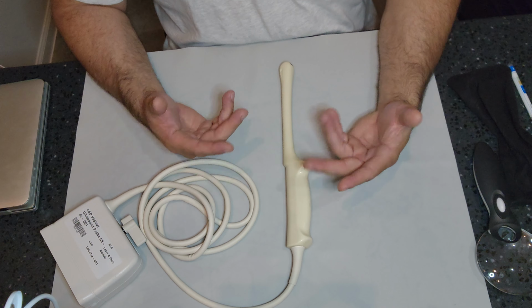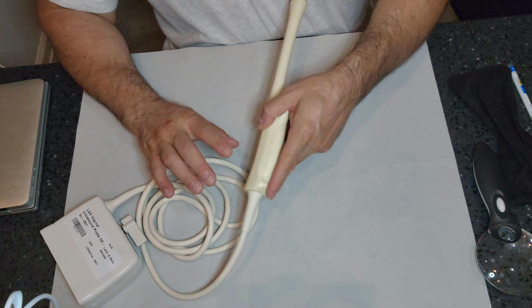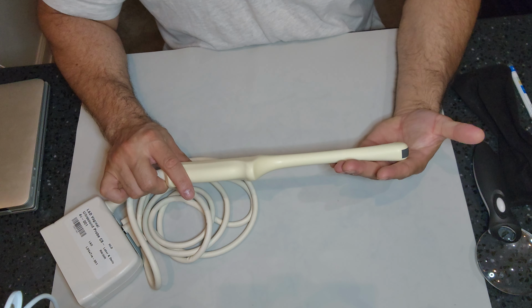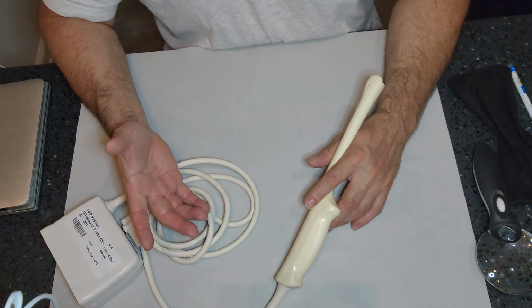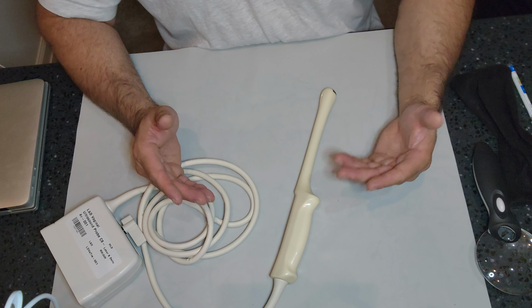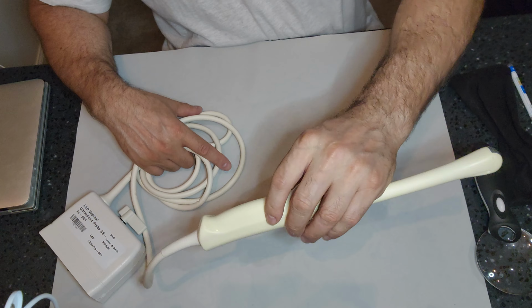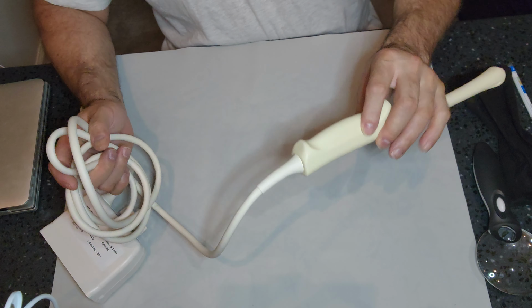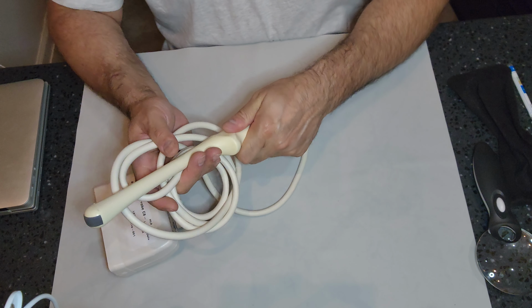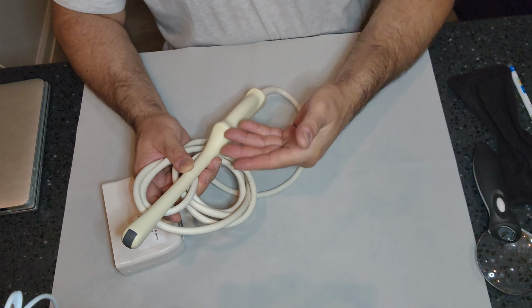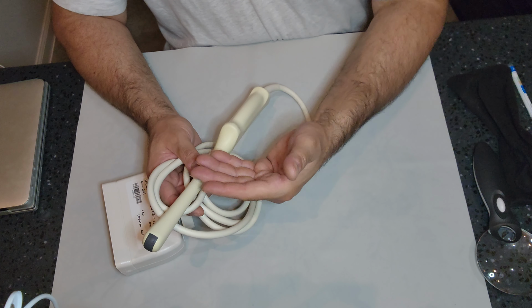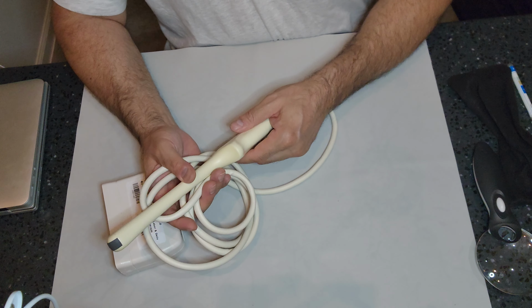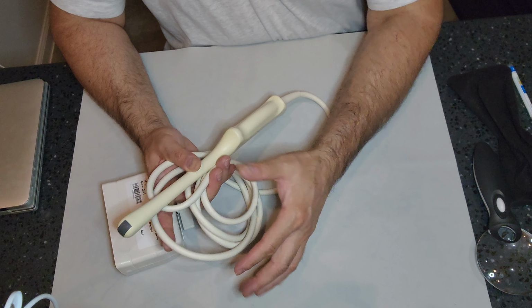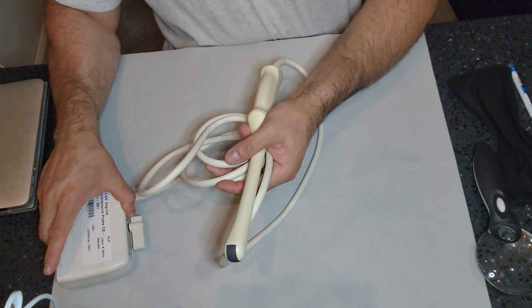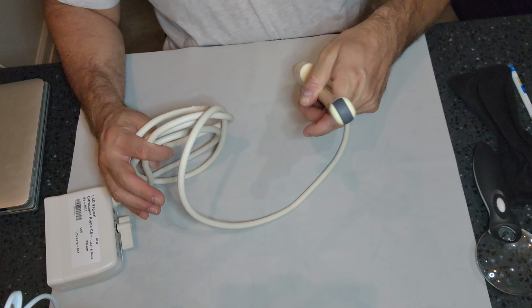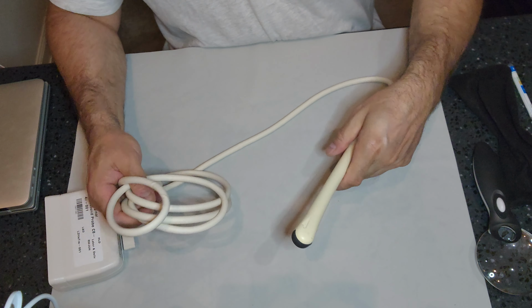What kind of gloves are we wearing? Are we wearing the dusty gloves that are in the corner, touching a high-level disinfected probe and placing it in a container that hasn't been disinfected? Or again, what is the IFU stating? Or are you using a special carrying case that separates the probe from the cord? Because this is high-level disinfected, this is intermediate disinfected. So if this is laying on this, you just undid all that hard work of high-level disinfecting the actual probe, touching a low-level disinfected item, and then the actual box. So how are you transporting it, and then how is it being stored at point of use? Is it coiled nicely? Is it hung?